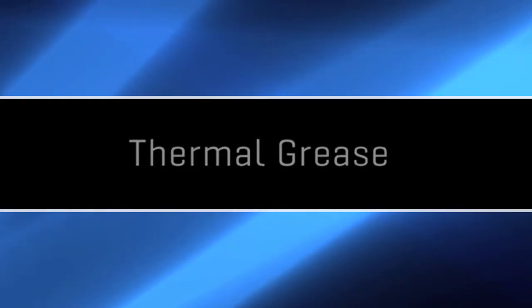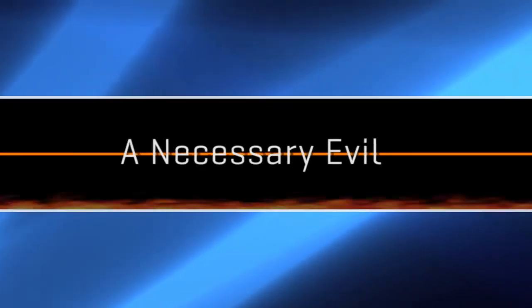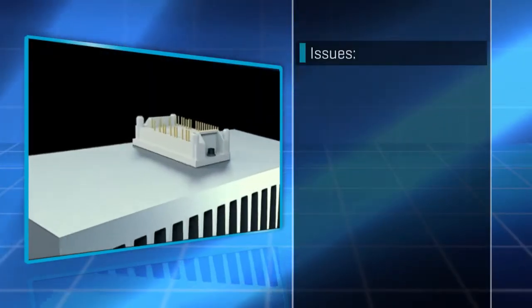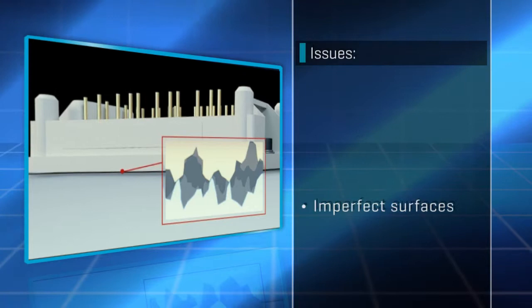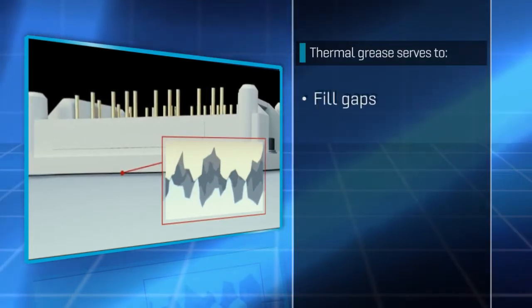Thermal Grease: A Necessary Evil. Modules are mounted on heat sinks to dissipate excess heat. Unfortunately, the two surfaces are imperfect, so contact is relatively limited. Thermally conductive grease serves to fill the gaps.